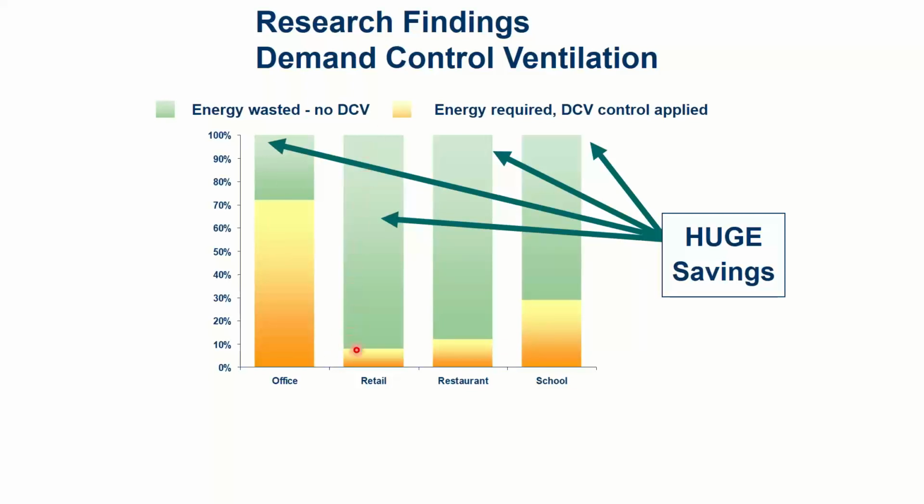Retail, it's like, I don't know what that is, 91% reduction, huge reduction. Because retail is designed for some peak crowd of people that hardly ever happens. It's like a Black Friday type crowd or something like that. It hardly ever happens. So I'm always way down here. Restaurants, same kind of thing. It's like an 88% reduction or something because they're designed for some kind of Saturday night dinner crowd. But Tuesday at 10:30 in the morning, it's not that busy there, right?